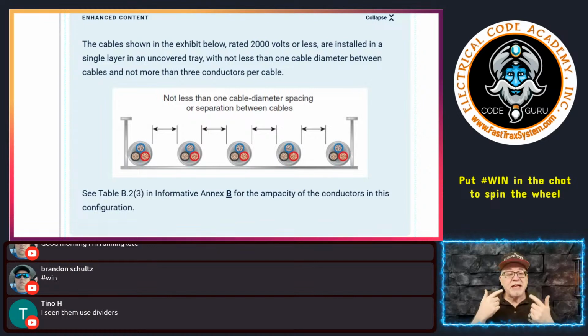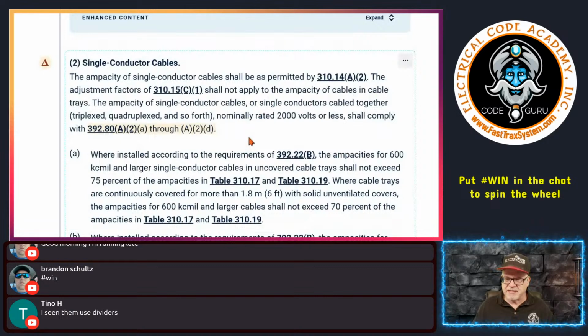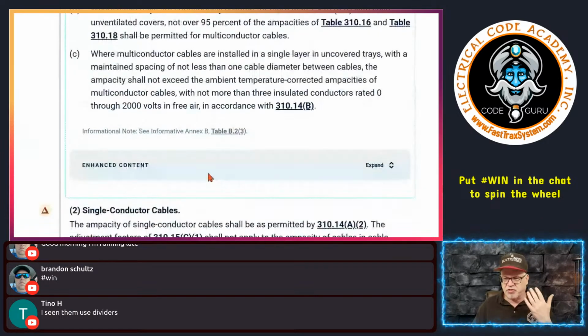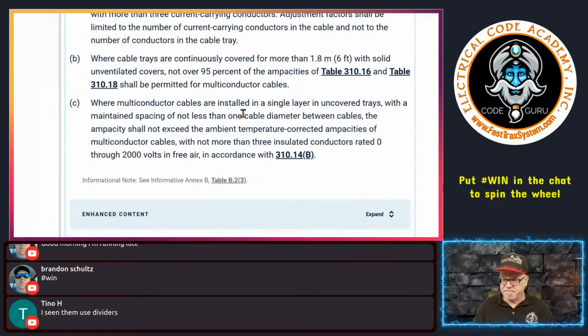What this means to me and you, it means that if I do this, then I can ignore anything about 310.15(C)(1) for the number of current carrying conductors. As long as I have not more than 3 insulated conductors in there, I can ignore all that, which you should be able to anyway. I can ignore all that, and I can use the ampacity straight from the table, 310.16. That's how I would prescribe this to be done, okay?